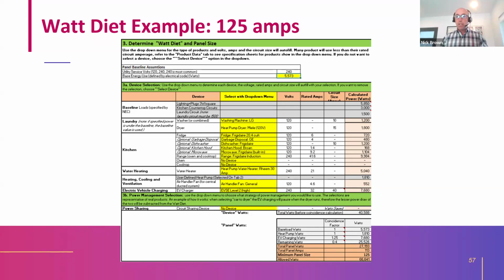What about battery storage? Does that need a larger panel size? No, not really, but it doesn't allow us to have a smaller panel size either. Solar is ignored in the calculation of panel size, even though it could potentially lower the peak draw, right? But the battery is usually installed in between the solar and the panel. Even your solar system can be installed without a breaker using what's called a meter collar, where the solar goes straight into the meter and doesn't tie up breaker space.